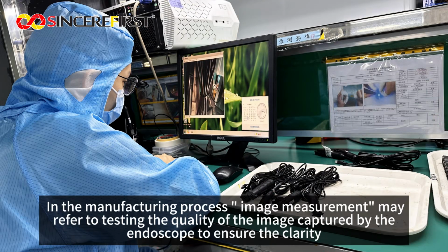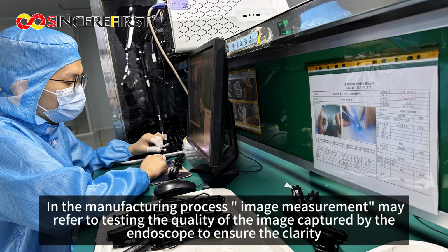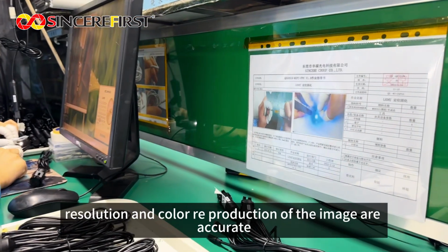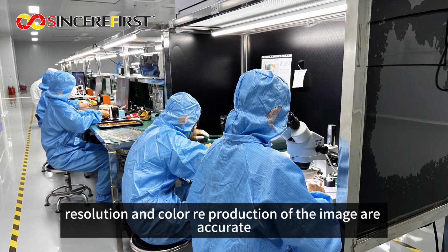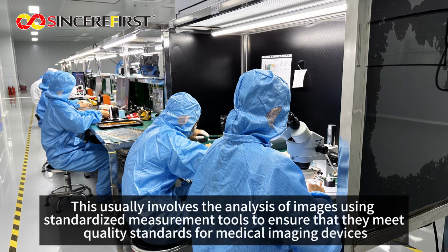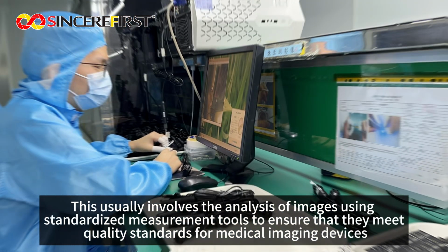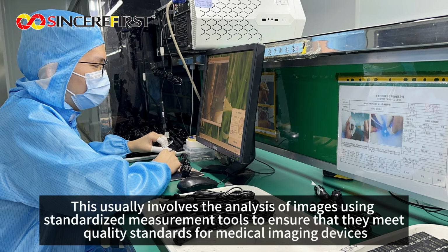In the manufacturing process, image measurement may refer to testing the quality of the images captured by the endoscope to ensure the clarity, resolution, and color reproduction of the image are accurate. This usually involves the analysis of images using standardized measurement tools to ensure that they meet quality standards.